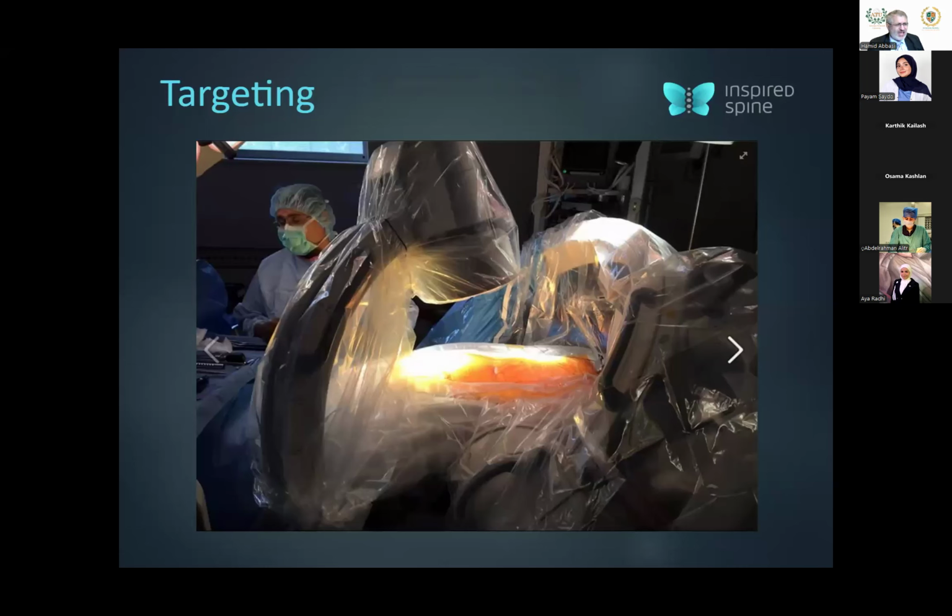That's not good enough. Additionally, what I need you to understand is that the machines you're using today are not the machines from the 1980s. You have an image intensifier, and they use like 1/200 to 1/300 the amount of radiation. As a matter of fact, in the United States, the rule is if you are 6 feet away from the source, 6 feet is 2 meters, actually less, you do not need the lead apron. This is their recommendation. So we are not using the same machine that used to produce a lot of radiation, but still we have to be conscious about it. No question.